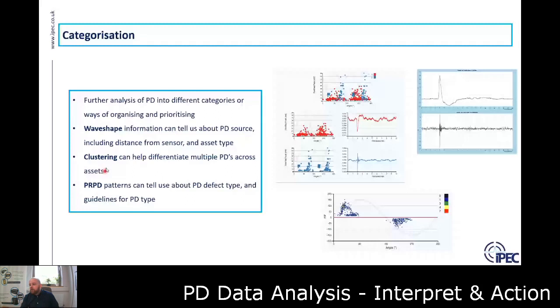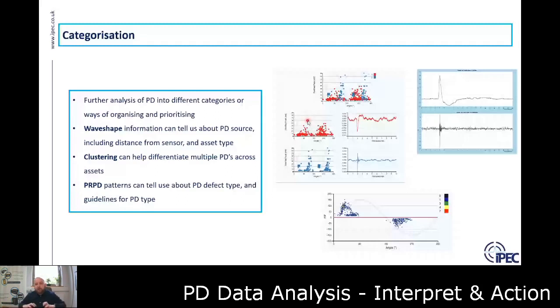The other technique is clustering — this is when we're seeing two PDs on one asset. It helps with wave shape analysis by separating those PDs. You can have automatic algorithms built into permanent monitoring systems for this. If you look at the top chart, the PRPD is very busy, but there are actually two PD sources in there. Running it through the clustering algorithm, the output below shows two different PDs detected by one sensor — the top one resembling a cable PD from further away, and the bottom one more typical of a local switchgear PD.